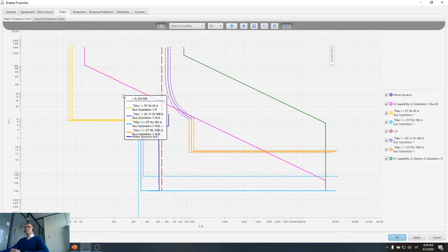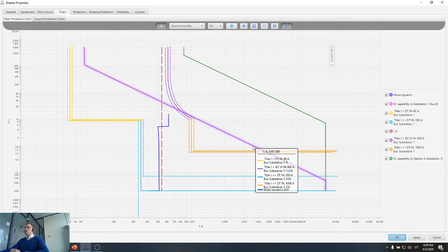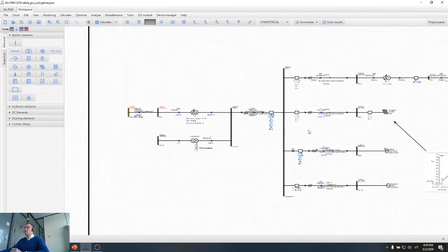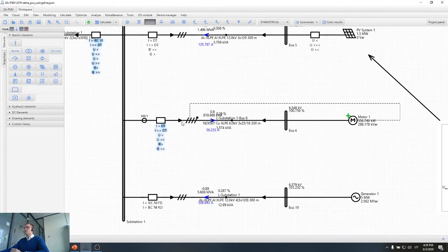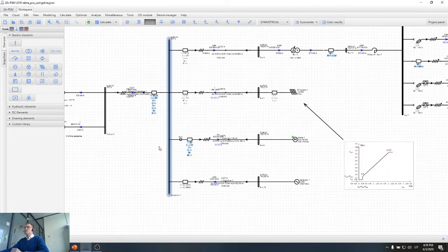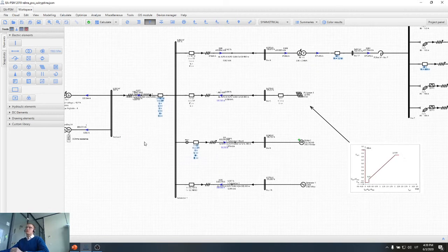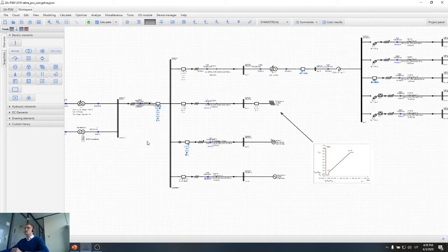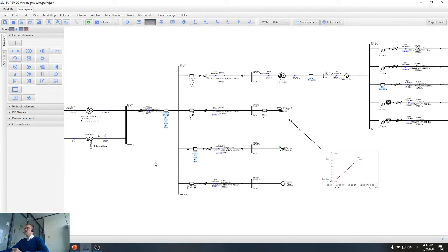Here is the capability of the motor, which we have worked with the protection. The motor was here. So in software it is possible to select cables, their capability limits, and select protection settings so that they will protect the equipment.